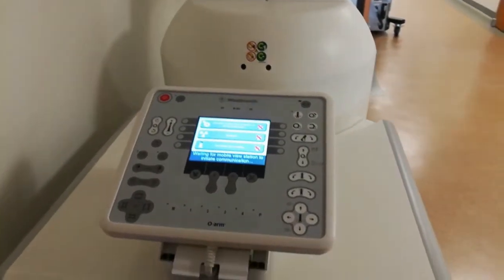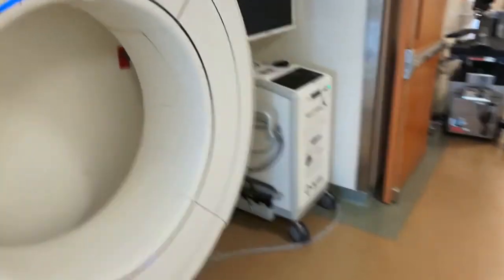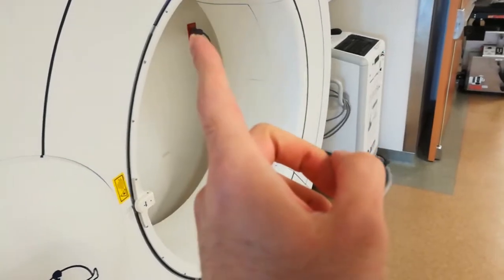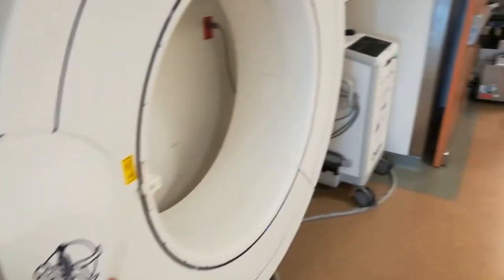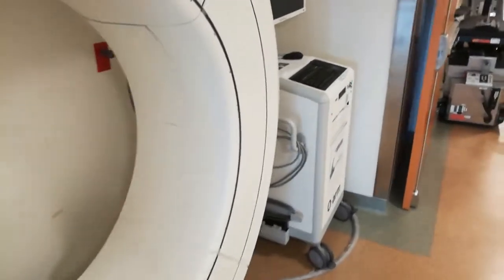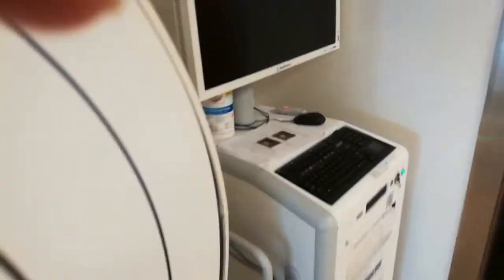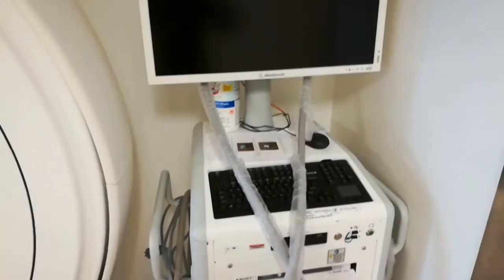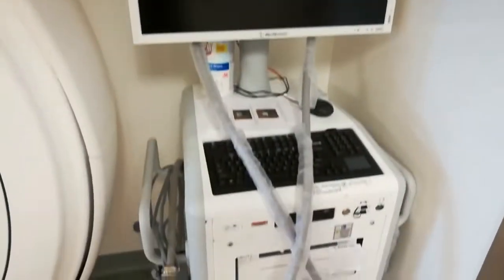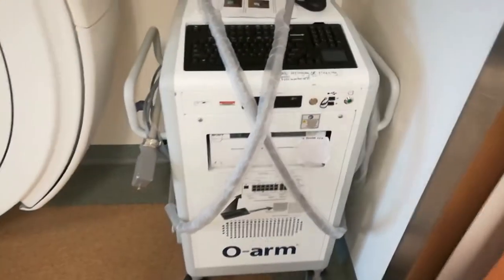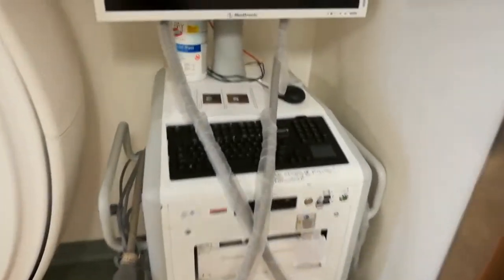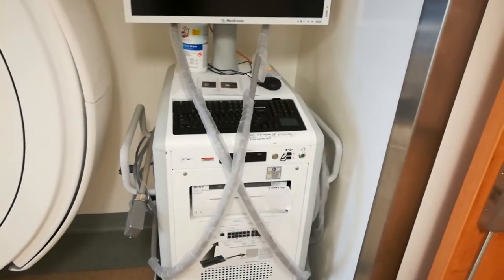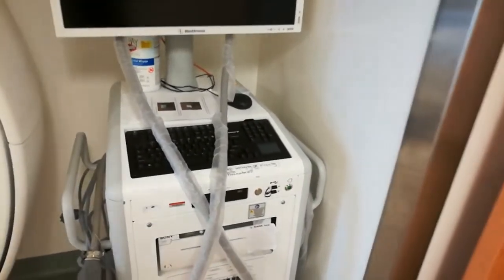So our O-arm is booted up now, ready to move. First thing we're going to do is, just like the C-arm, you unplug from the wall before you unplug from each other. And the opposite applies when you're hooking them back up. So I'll see you guys in the room. It doesn't have to be pretty, guys, just get the machine in the room before it runs out of batteries. So I'm going to take the monitor in first, because the O-arm will be closest to the double doors.